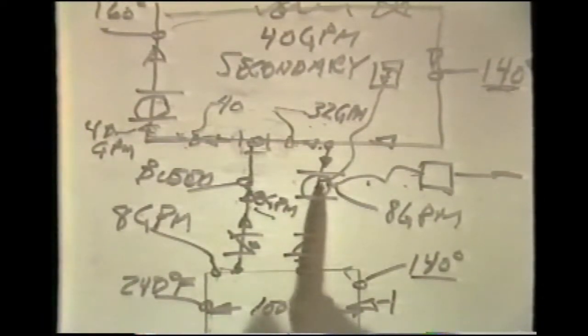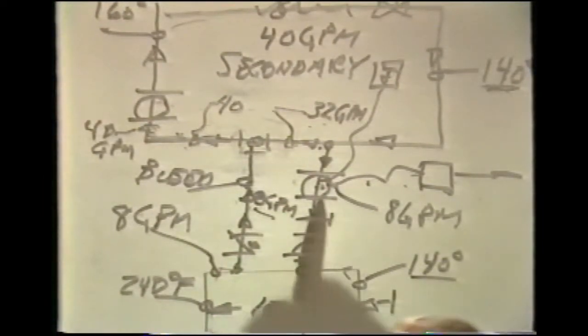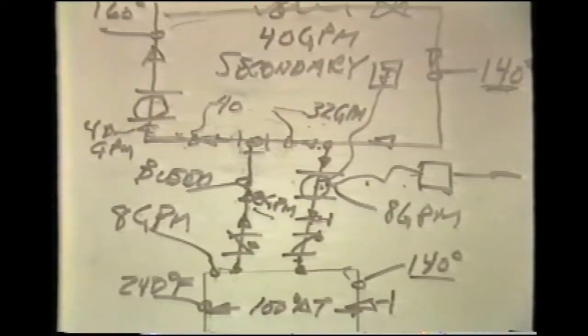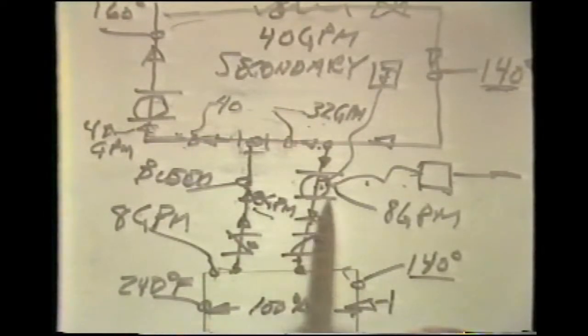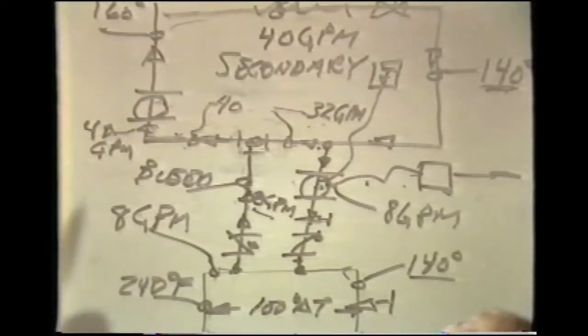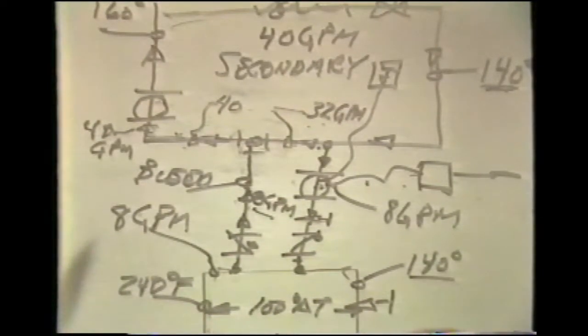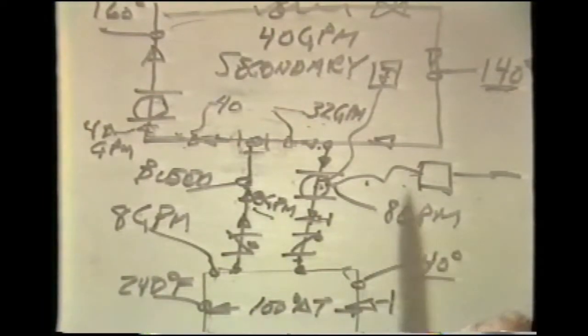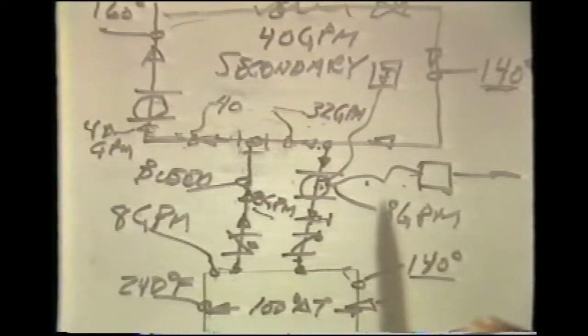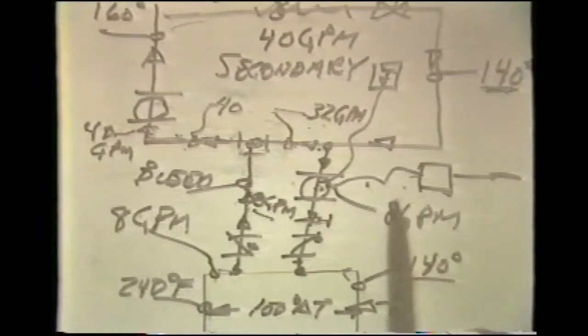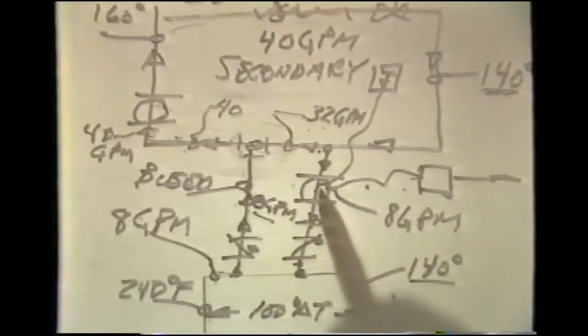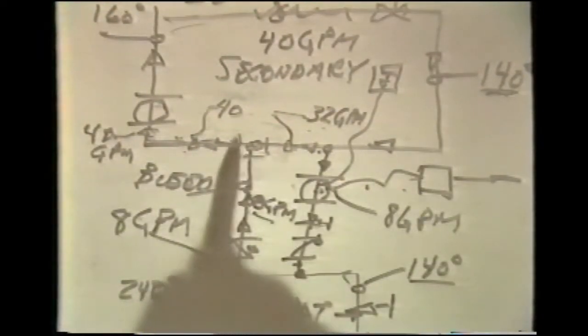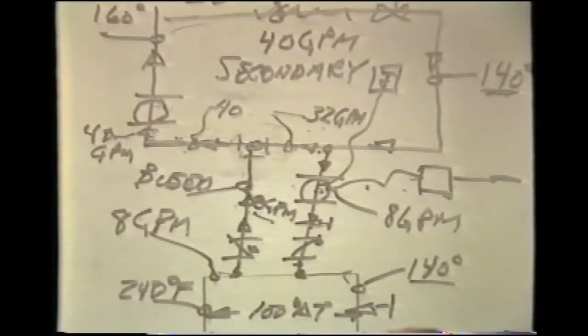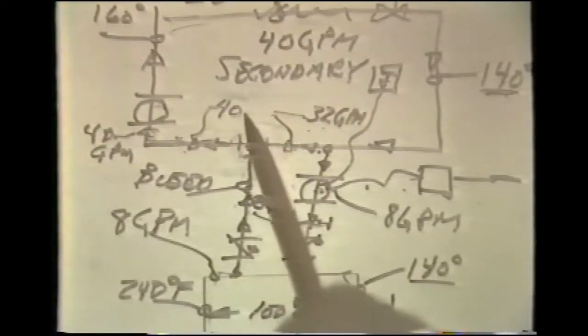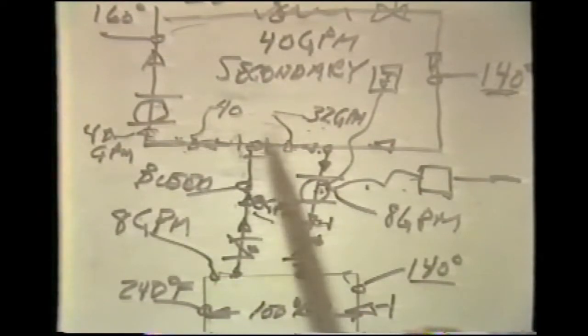The only important point is that we have to adjust the pump so that we get out of the starting winding mode in terms of operation of that pump. Given that circumstance, we have, for example, an injection pump in our schoolhouse used for control of baseboard water temperature and panel heating, which has been in operation for 25 years without ever having a need for service except for an occasional oiling of the pump. We can, because of the quick and instantaneous cycling of the pump, maintain incredibly close control of water temperatures in the secondary circuit, whether this, in this case, be on reset or for a single water temperature.